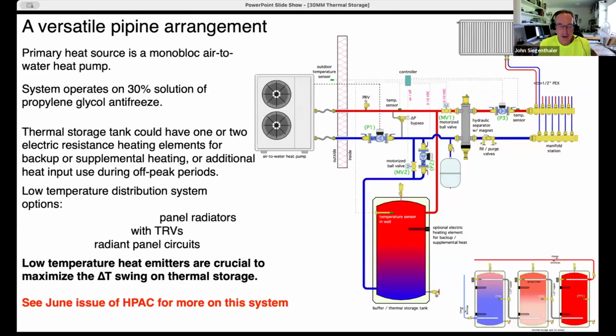Again, this is the June issue of HPAC, and I'd encourage you to look at that on the website because we don't really have time to go into great depth on the different modes of operation. But that schematic you're looking at is based on an air to water heat pump, a monoblock heat pump. The red lines represent the hot mixture of antifreeze and water coming in. The valving and the circulators can all be controlled, and essentially we can take that hot water coming in and send it directly to the load. Over on the far right of the schematic, I'm showing panel radiators on what we'll call a home run distribution system with a variable speed circulator, a very simple, scalable system, excellent for low water temperatures. The panel radiators can be sized to operate in the range of 110, 120 degree Fahrenheit water.